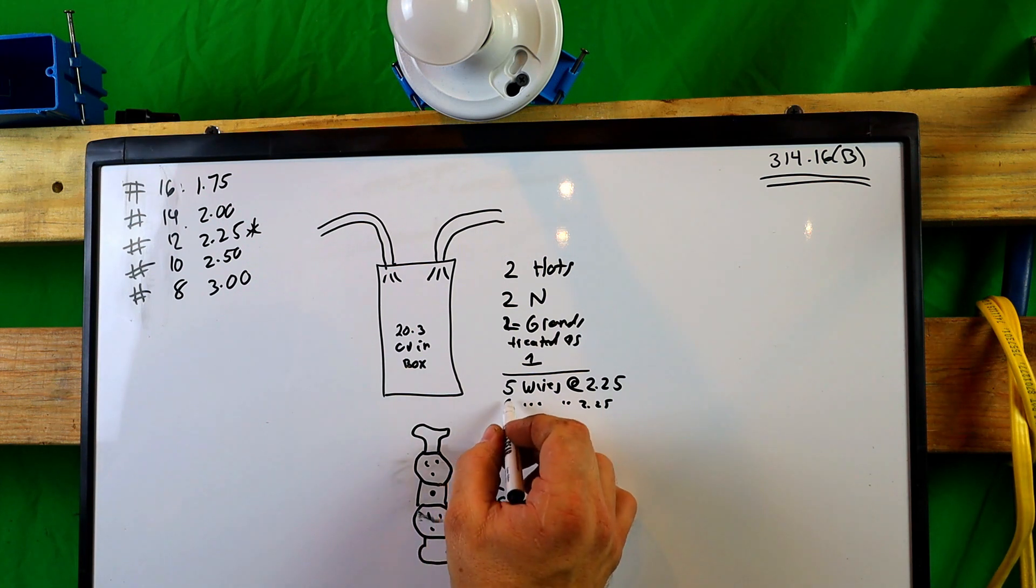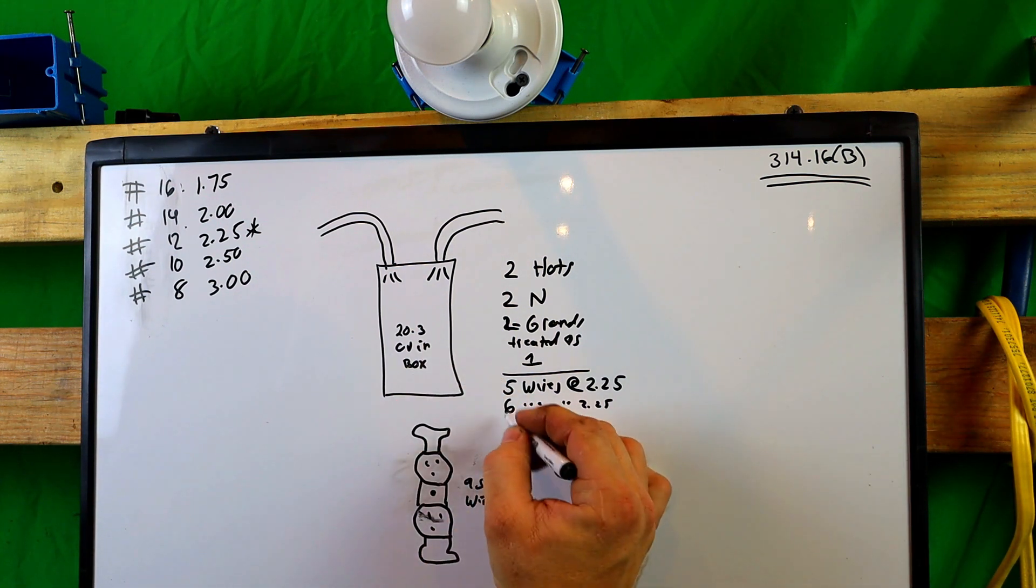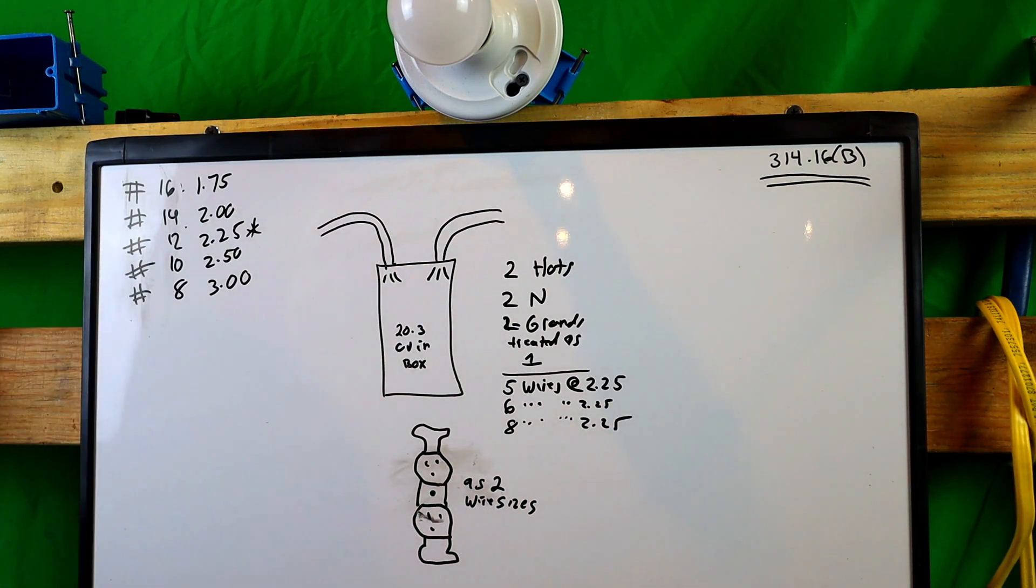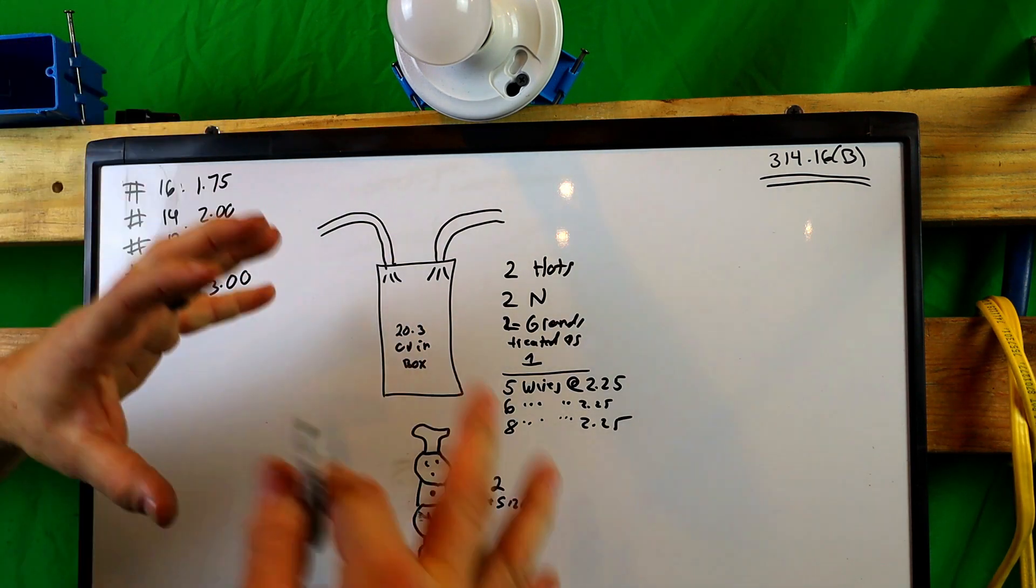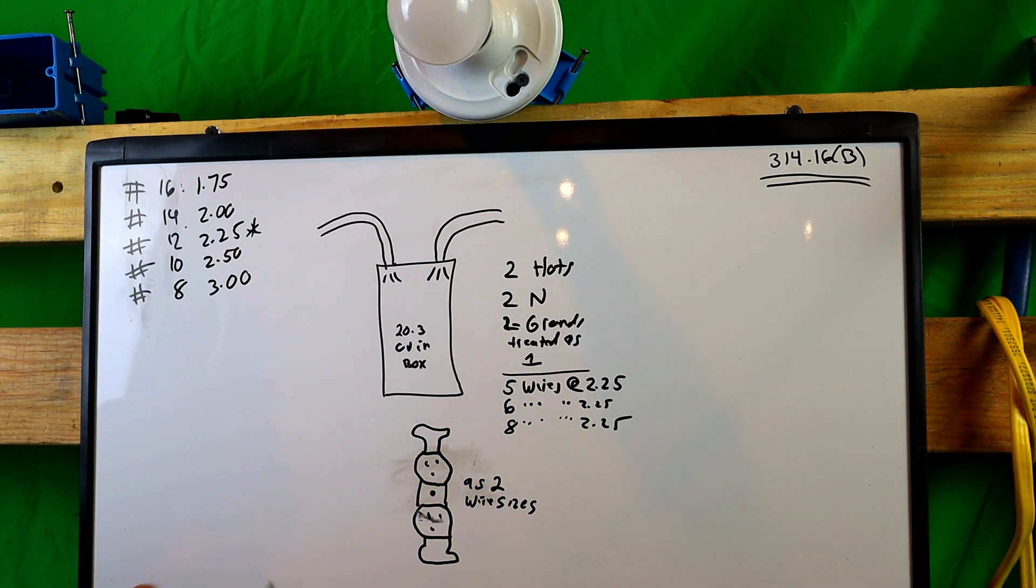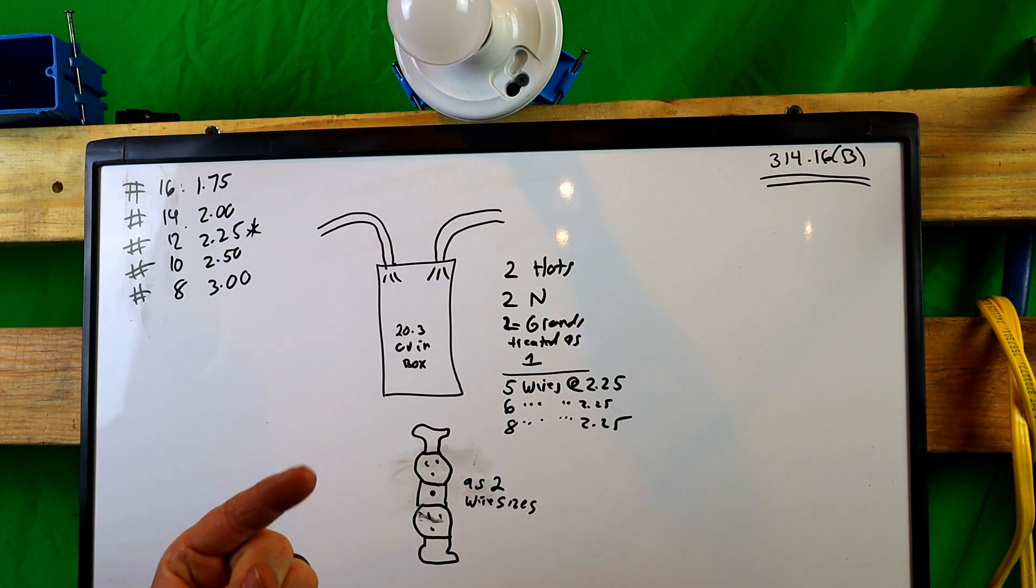So every device that you use has to be counted as two wire sizes. Alright. So now what we got, we have, we had six, right? So we have two more. So now we have eight times 2.25. Alright. Is that all we have? Yes. Now we're going to get into more deeper. This is just the basics right here. I'm going to dig a little deeper later and tell you about, do you count the wire nuts? Do you count extra wires you put it in there? If this was not this box and it had to put a Romex connector, would you count that?